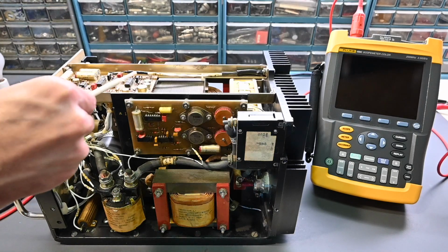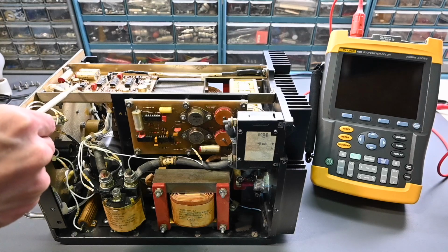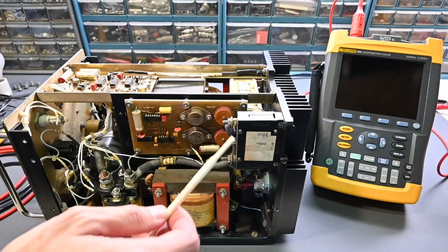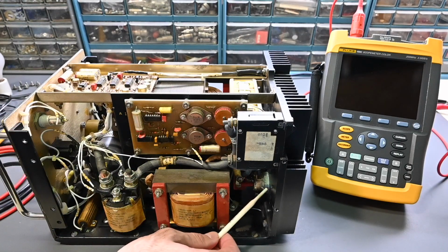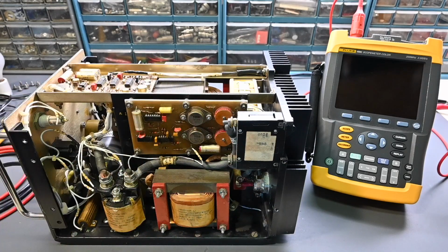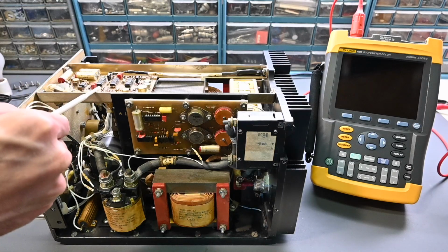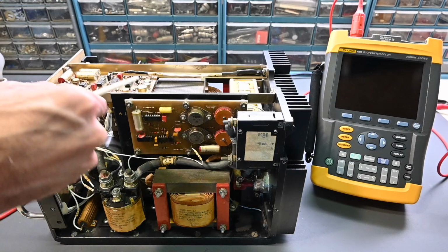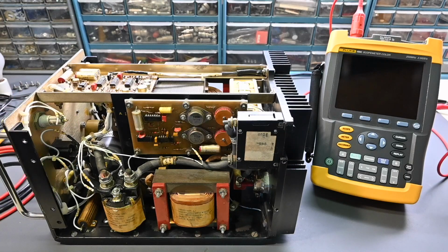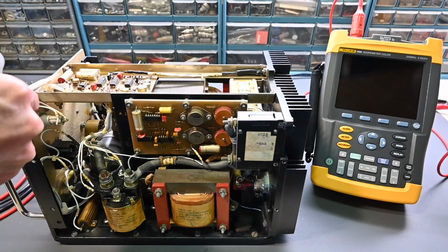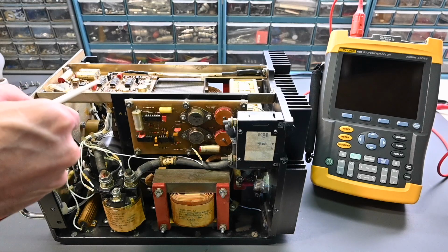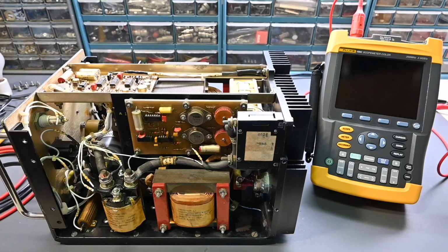This circuit board doesn't seem to be connected in any way to the SCRs. There are 2 SCRs that do the main switching - one's right here on the heatsink, and the other's kind of buried over on the other side. The SCRs have to be turned on with a gate turn-on signal, but this circuit board doesn't seem to be doing any of that. In fact, I don't see any oscillation or anything going on up here that would be running the inverter at that 60 hertz frequency. So this all seems to just be sort of a control, maybe a protection type circuit, possibly a voltage regulator as well.